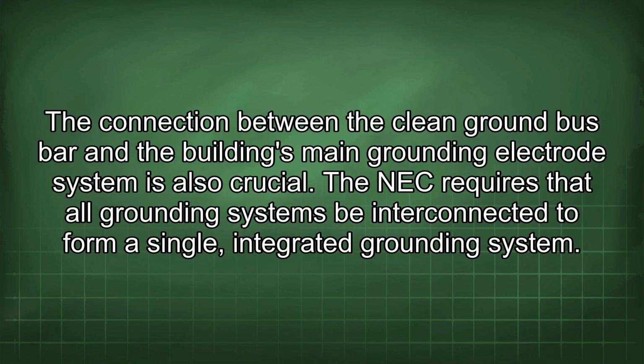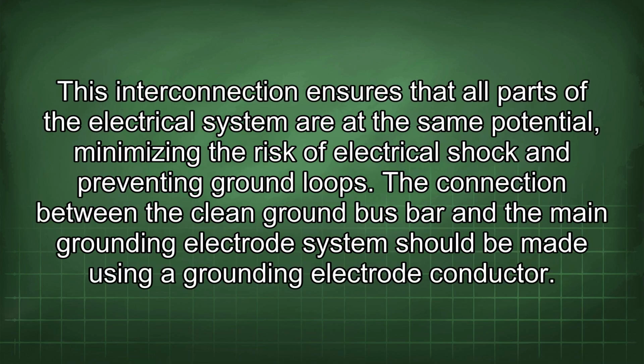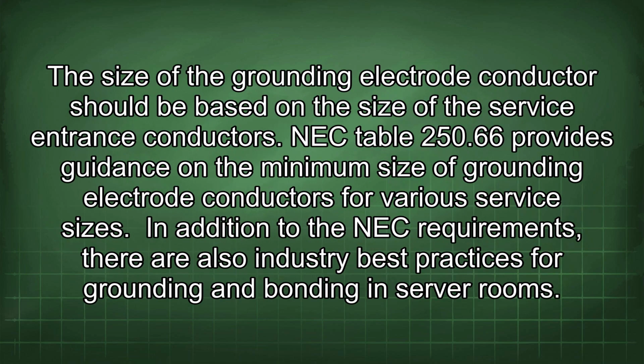in North America. The connection between the clean ground bus bar and the building's main grounding electrode system is also crucial. The NEC requires that all grounding systems be interconnected to form a single, integrated grounding system. This interconnection ensures that all parts of the electrical system are at the same potential, minimizing the risk of electrical shock and preventing ground loops. The connection between the clean ground bus bar and the main grounding electrode system should be made using a grounding electrode conductor. The size of the grounding electrode conductor should be based on the size of the service entrance conductors. NEC Table 250.66 provides guidance on the minimum size of grounding electrode conductors for various service sizes.